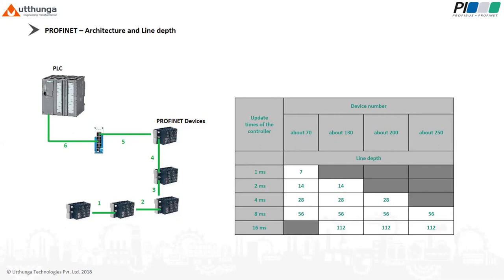Then what is a hop? You'll be having a question, right? A hop, in the sense, you can see in the left side image, we have connected 5 devices and one switch in between. Thus, data will have 6 hops to reach the controller. For example, if I have a PLC with a cycle time of 1 millisecond, as per the standard, I can go up to a maximum of 7 hops. So after the 6th hop, I will connect a switch.